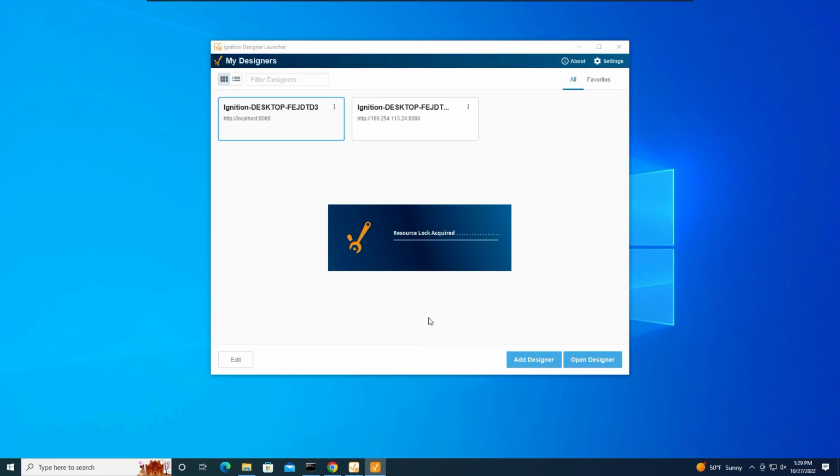And the way the MQTT engine is set up in Ignition, anything that is being published to that data broker will be brought into Ignition, and you'll see the tag structure that it makes within Ignition. So there'll be an entirely separate tag provider in Ignition for the MQTT engine, and I'll be able to browse to the specific topic path that we're publishing the heating temperature on.